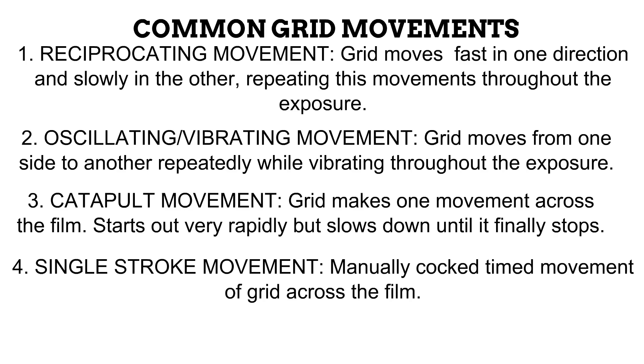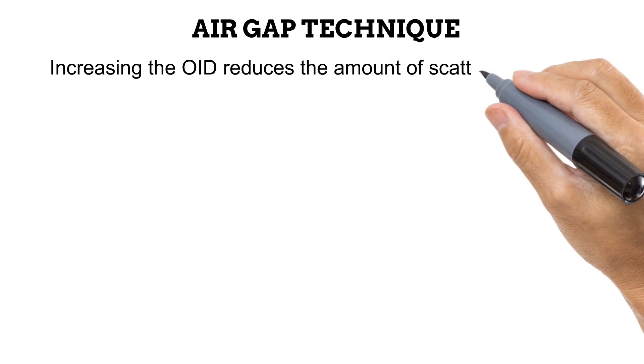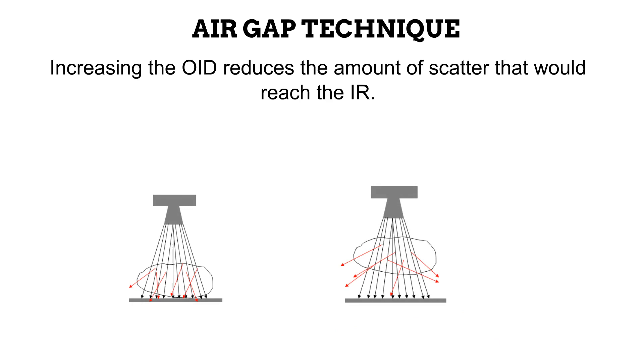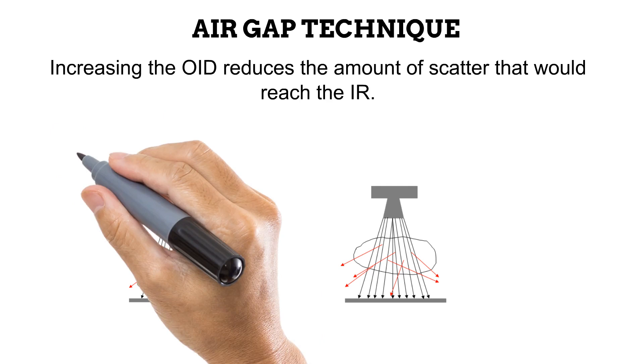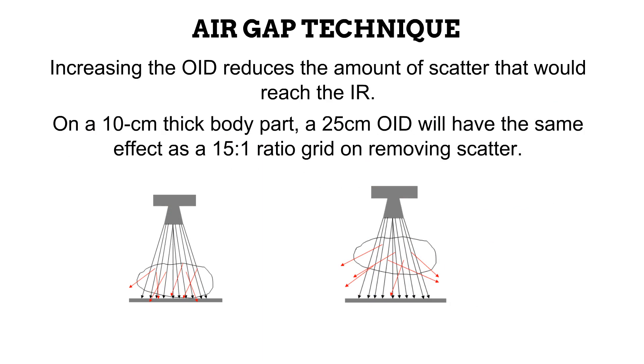Now that we have looked extensively at grids, let us look at the second method of preventing scatter from reaching the image receptor — the air gap technique. It involves introducing distance between the anatomical part and the image receptor, an air gap. With the object in contact with the receptor, a lot of scatter reaches it. However, when an OID is introduced, the deflected scattered photons continue to diverge out of the range of the image receptor. It has been observed that on a 10 cm thick body part, a 25 cm OID has the same effect as a 15:1 ratio grid. While the air gap technique is helpful, grids are still the preferred option because OID causes unsharpness and magnification.